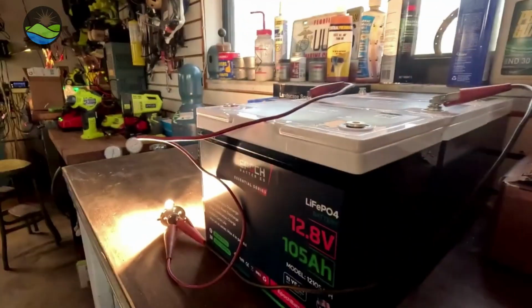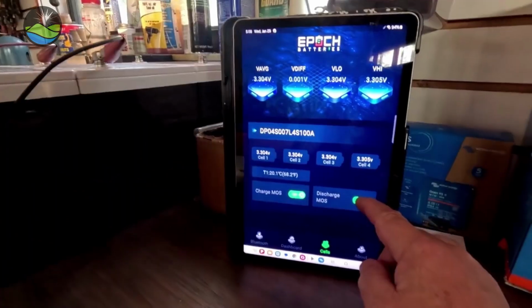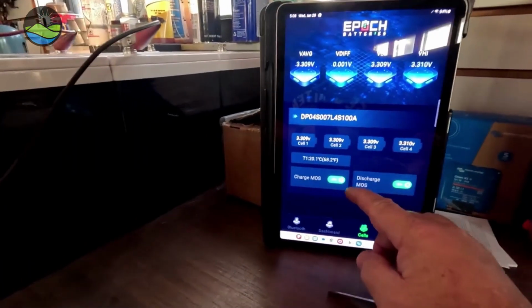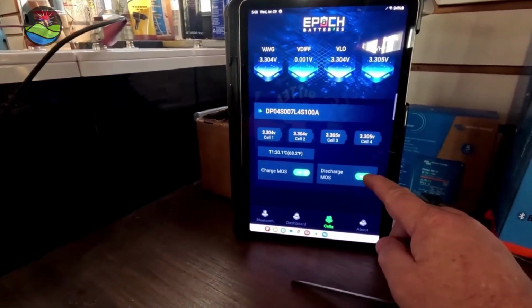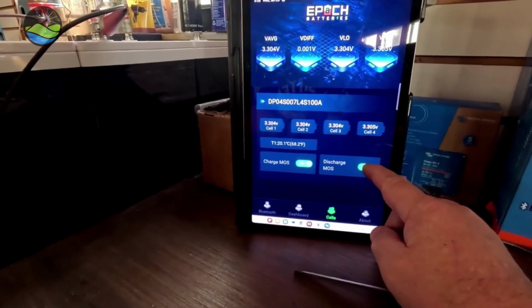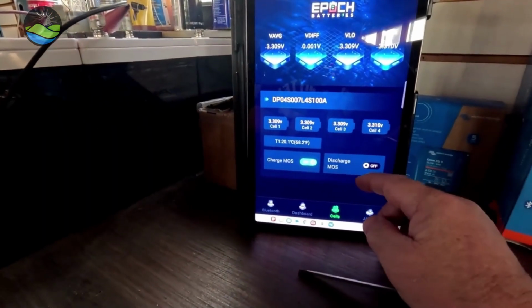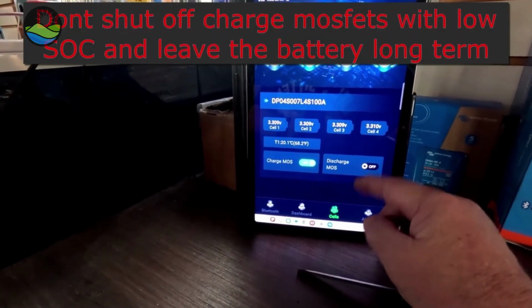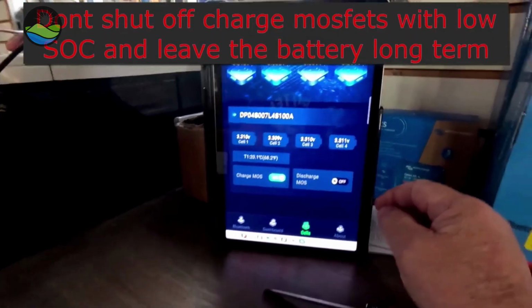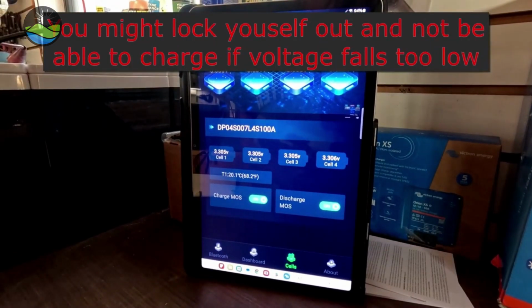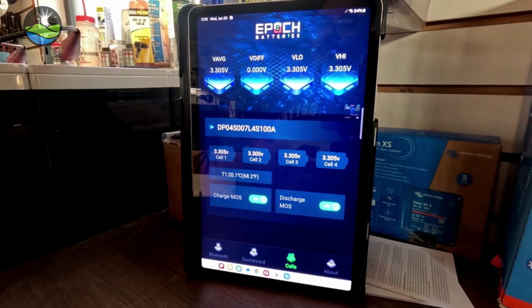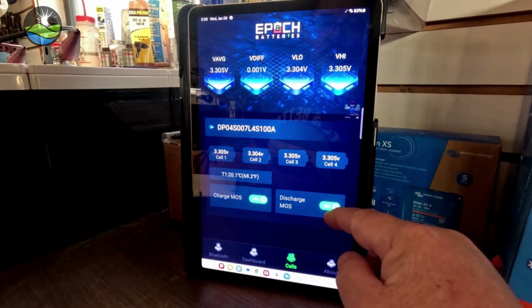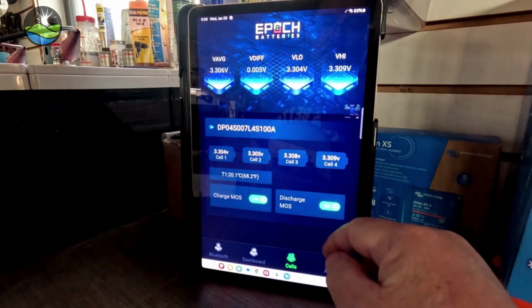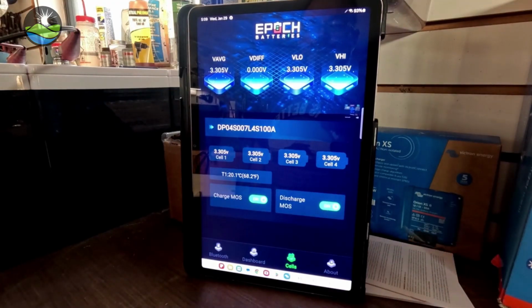If you're just messing around in the garage, or present on the boat trying to test something, yeah, you can go ahead and use them. But generally speaking, don't shut off discharge MOSFETs with the battery at 10% and go away for 6 months, because it may discharge below a certain amount and you might never recover it. So typically don't mess with them. If you need to shut it off, you really should have battery isolation switches on these things, and that's the preferable method for long-term storage. Don't use these discharge or charge MOSFETs for that.